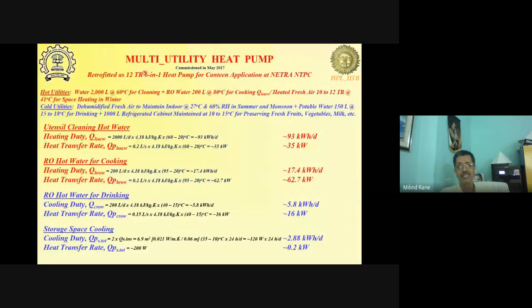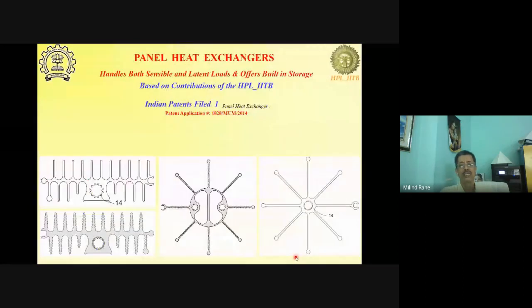Now, a 12-ton compressor-based heat pump can never give you this unless there is storage. So the built-in storage is able to do that. And then we have RO water heating and RO water cooling for drinking purpose, and the refrigerator. Refrigerator load, as you can see, is extremely small. Then we have technology for panel heat exchangers, which are radiant panels for heating and all those things.